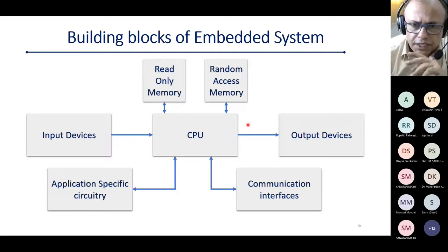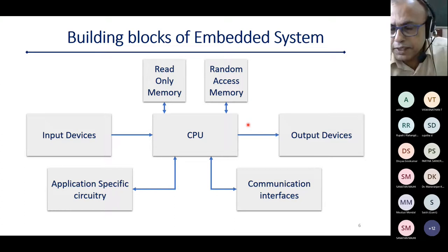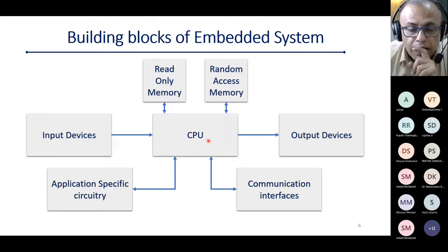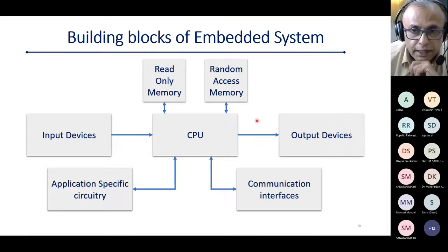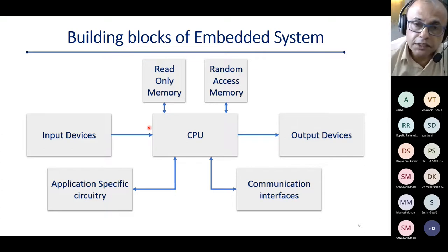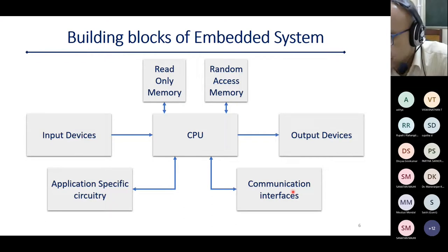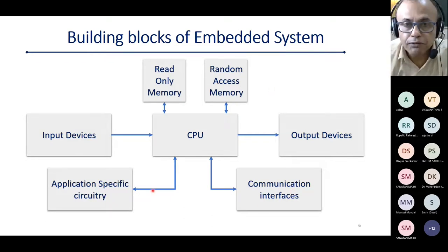So there you have two components, the sensing component and the delivery component, the drug delivery component. And together it is known as a system. This has to be carried out using this specific circuitry and CPU, and this will be electronically connected with the mechanical component also. On the other side, the sensor part will only deliver the output of the glucose sensor in electrical form, and the whole thing will be performed. Okay, as well as you can communicate the data. What is the glucose level every hour? It will sense, and this signal or the data will be transmitted to the outside also. This is the whole part with the example I have given you.